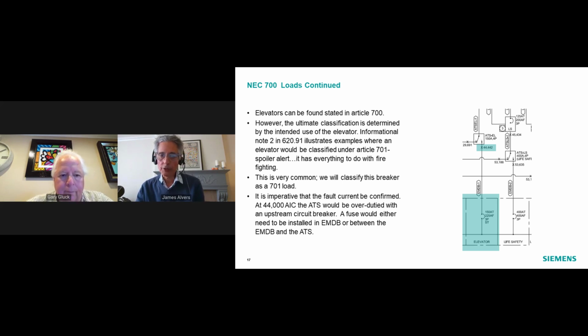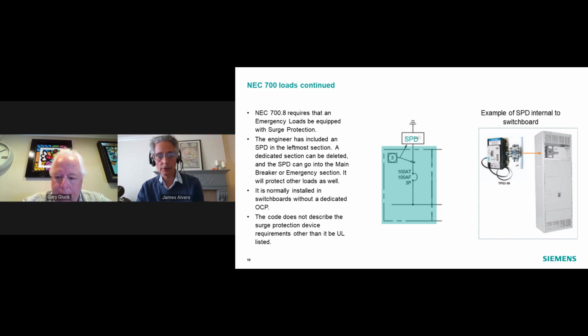You'll notice here at this ATS, the engineer has said there's a fault current of 44,442 amps. So this ATS is probably not going to be able to meet that requirement. It's a 150 amp 4-pole ATS. Most likely a fuse would be needed somewhere ahead of that ATS to meet that requirement. I'm going to talk more specifically about ATSs in a little bit here.